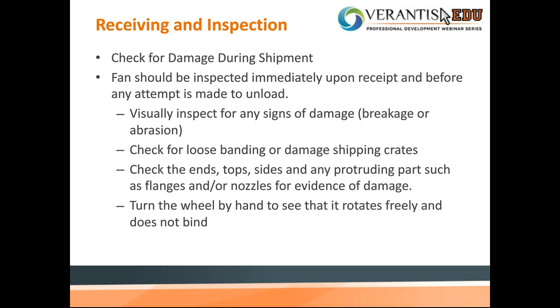Now, it all depends on how the fan is shipped. Sometimes a larger fan may just be on a standalone crate that's bound down to a trailer, but other times some smaller fans are shipped via LTL. So they may be dropped off at a bunch of different shipping points before it actually comes to your end location. So we need to check the ends, the top, the sides, and any protruding parts such as flanges or nozzles for evidence of damage.